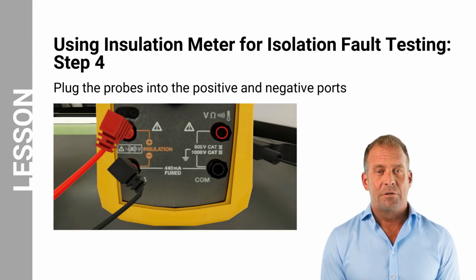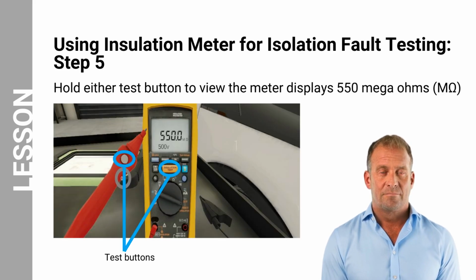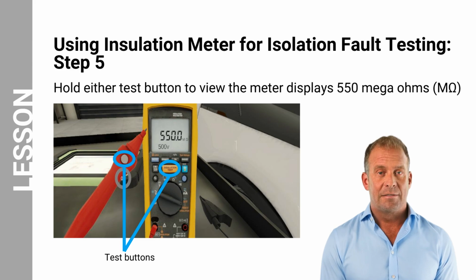Step 4. Plug the two probes into the correct positive and negative ports. Step 5. With the test leads not connected, press and hold the test button to view how your meter displays an infinite measurement. The meter will display 550 megaohms when measuring an open circuit while set to the 500-volt range.